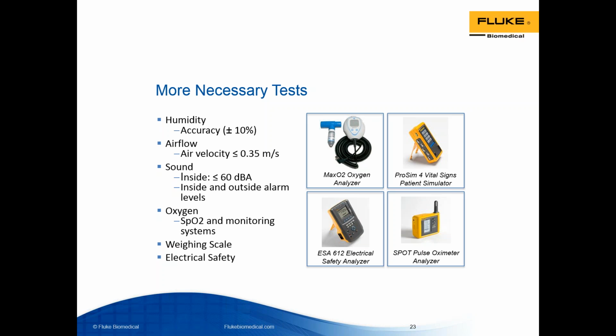So it is important also to measure the scale using a series of calibrated weights to make sure it's accurate. And finally, electrical safety. Most manufacturer performance inspection procedures require electrical safety tests, including ground wire resistance and chassis leakage. So keep an electrical safety analyzer. I posted an example of a Fluke Biomedical one, the ESA 612.